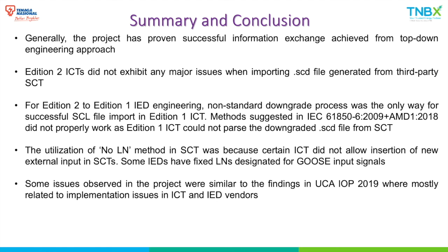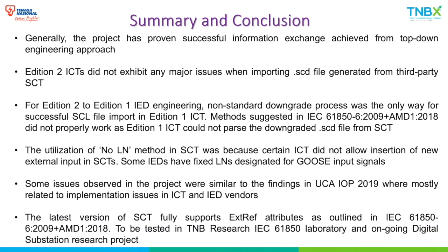Some of the issues mentioned earlier were also observed in the UCA IOP 2019 final report, mostly related to implementation issues in ICT and IED vendors. Last but not least, the latest version of SCT we used for the project now fully supports external reference attributes as outlined in IEC 61850 Part 6 Edition 2.1. This is to be tested in the ongoing IEC 61850 Digital Substation Project at the TNB Research laboratory. I personally have not yet tested this attribute, but I look forward to the actual work, hopefully after the lockdown ends by the end of this month.